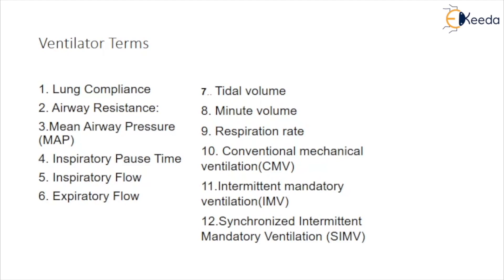Conventional Mechanical Ventilation (CMV) provides a forced tidal volume and respiratory frequency to achieve the desired minute ventilation. Intermittent Mandatory Ventilation (IMV) allows the insertion of a variable time delay between each breath. The Inspiratory-to-Expiratory phase time ratio (I:E ratio) signifies the ratio of inspiratory interval to expiratory interval of a mandatory breath, normally limited to 1:1; the inspiratory time should not exceed 50% of the total ventilator cycle time. Synchronized Intermittent Mandatory Ventilation (SIMV) represents a combination of machine ventilation and spontaneous breathing, enabling the patient to breathe spontaneously in regular CPAP cycles with a mechanical mandatory ventilation stroke providing minimum ventilation during the remaining cycles.